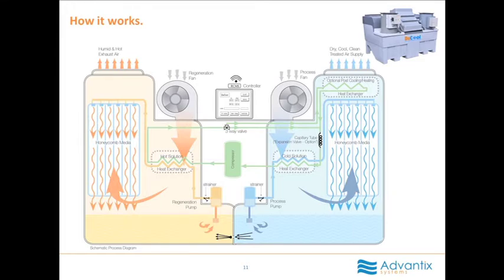I'm going to cool down that liquid desiccant. And this is what we're talking about, a chilled desiccant earlier. Now if I bring it up here, it's both cold and a drying agent. So the air that I'm getting out of the top, once I pass it over there, will be cooler and drier than the air that I brought in from outdoors.